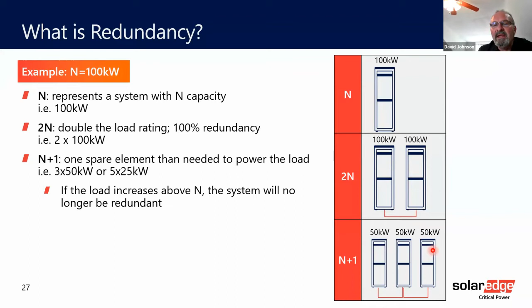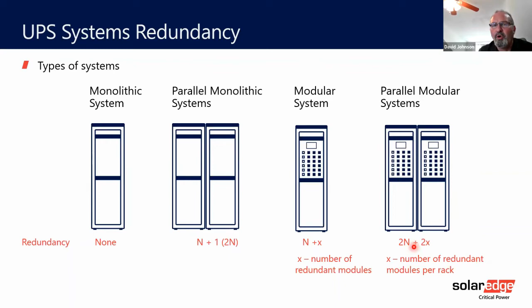So with monolithic systems, again, there's no redundancy. You're just covering, in our example, 100 kW. Parallel monolithic, we have to add an additional unit. It becomes N plus 1, but in reality it's 2N, which is a much more expensive approach. With a modular system, you can cover N. In our example, we had 240 kW, 8 times 30 gives us 240, and we add the 9th unit for redundancy. Or if we want, we can go to 2N plus 2 by going with 2 modular systems. Depending on what level of module, if you have 1 redundant unit, it would be 2N plus 2. If you have 2 redundant units per system, it's 2N plus 4, etc. I think you get the idea.